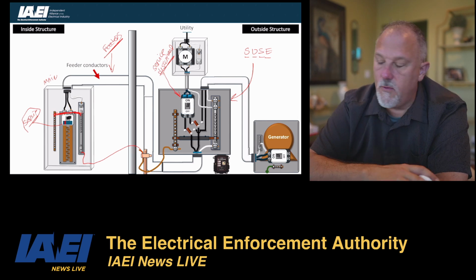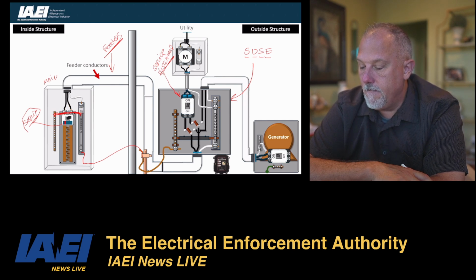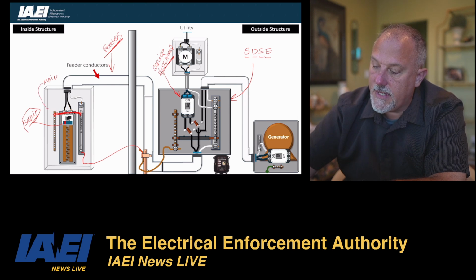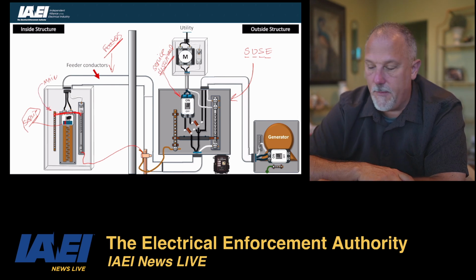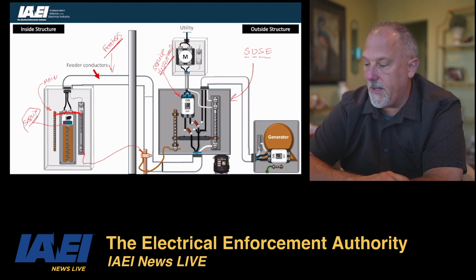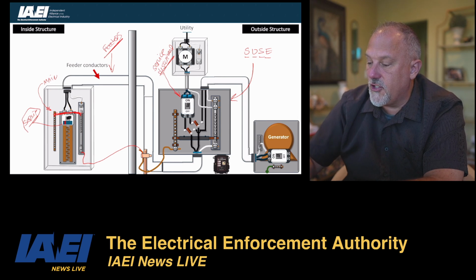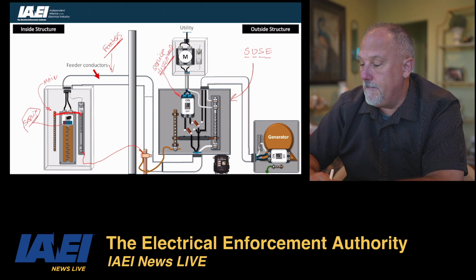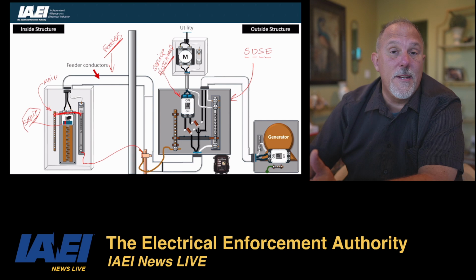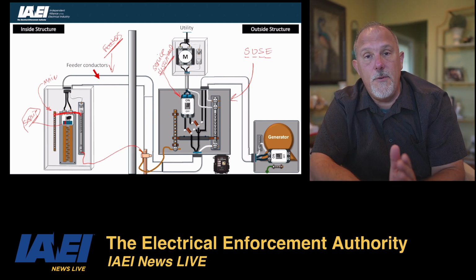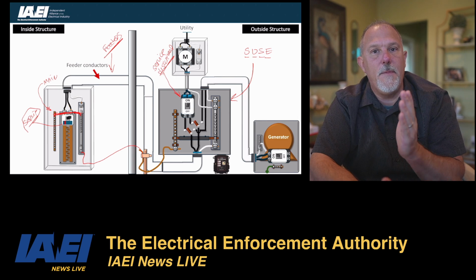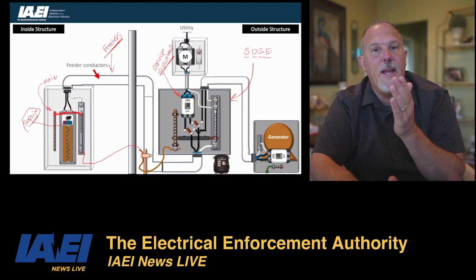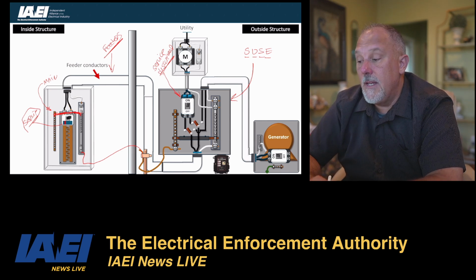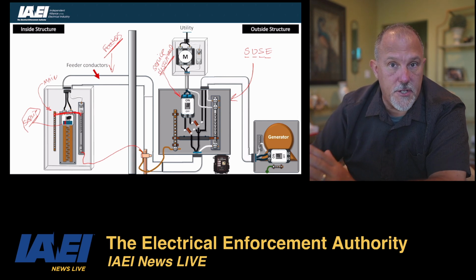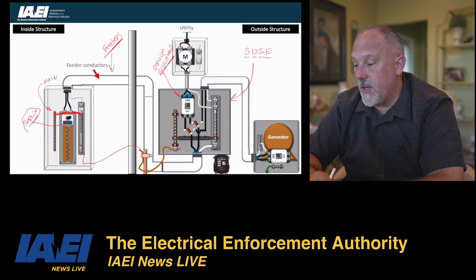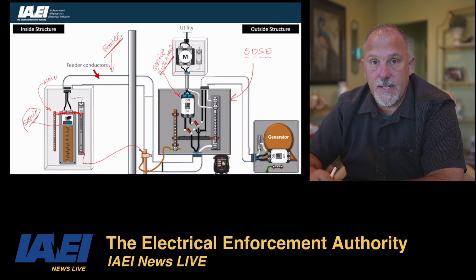There's no technical reason why this breaker that's in this panel board can't remain as your main breaker, and the bonding and grounding be done there, and this transfer switch circuit breaker still be SUSE rated. You could even bond it and ground it there. There's nothing in the code that says you can't ground and bond multiple times ahead of the service disconnect. But in this case, you are establishing a new service disconnect when you put this transfer switch in. That is now your service disconnecting means.